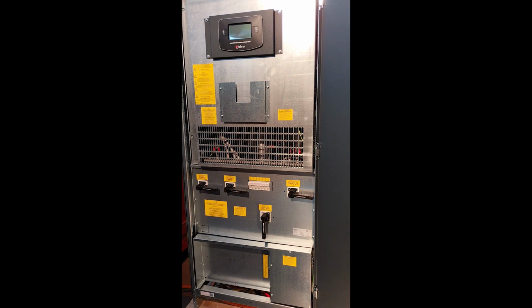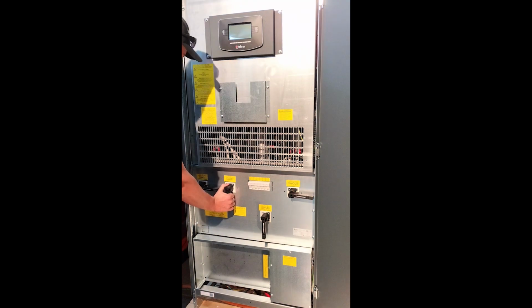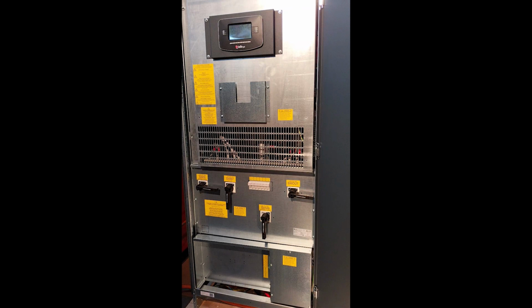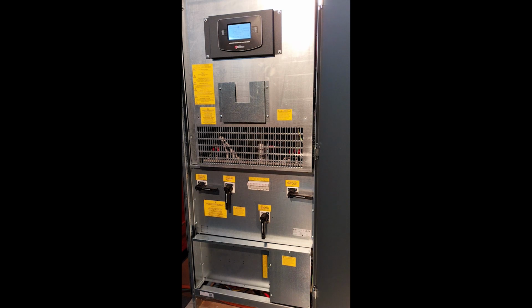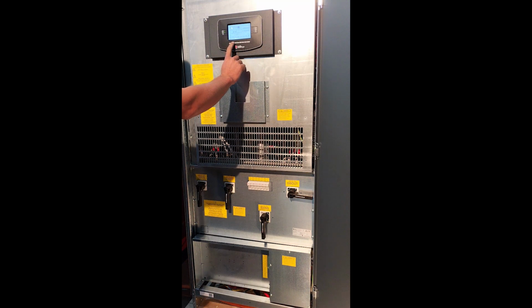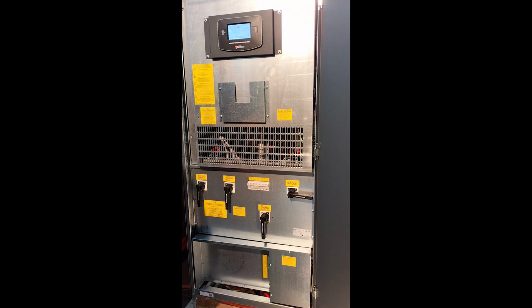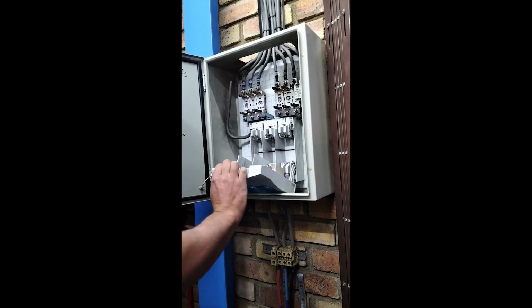Right, we're going to start by turning the bypass switchgear on first. The UPS power controller is now powered up. Next we turn the main input switchgear on, SW-in. Next we're going to turn the output switchgear on, and so our load will have power. Okay, time to close the battery isolation.